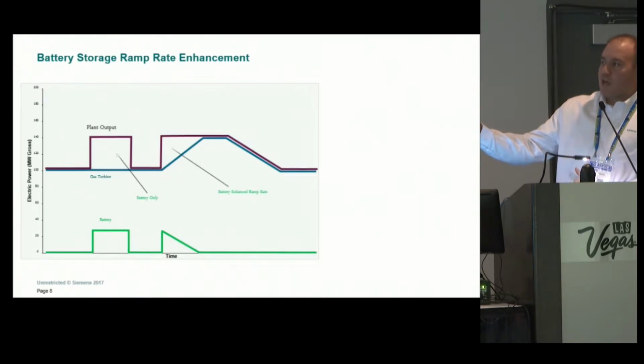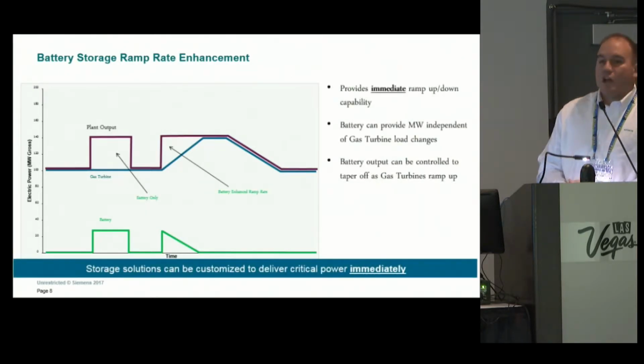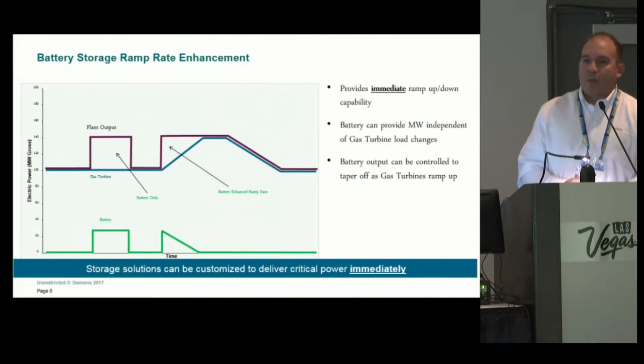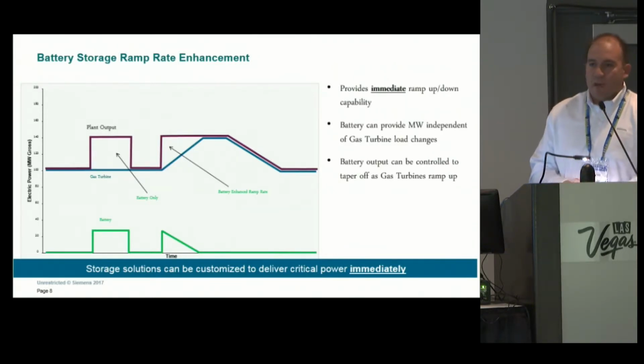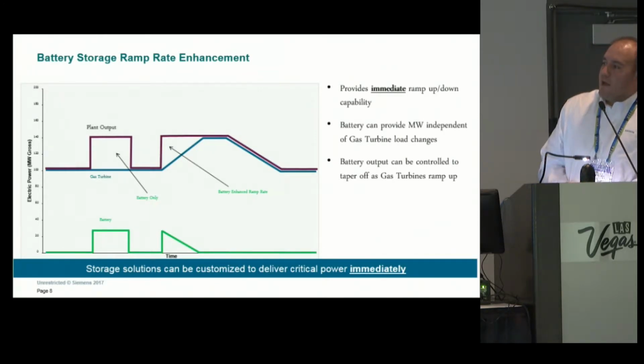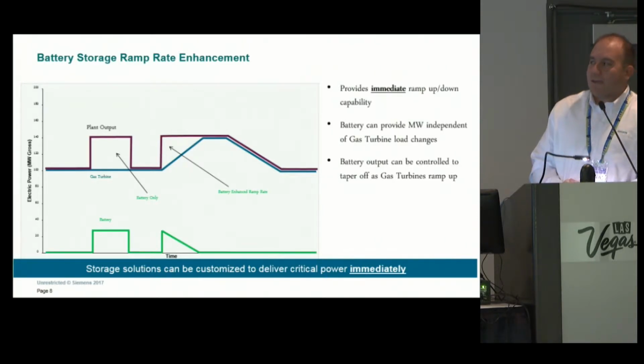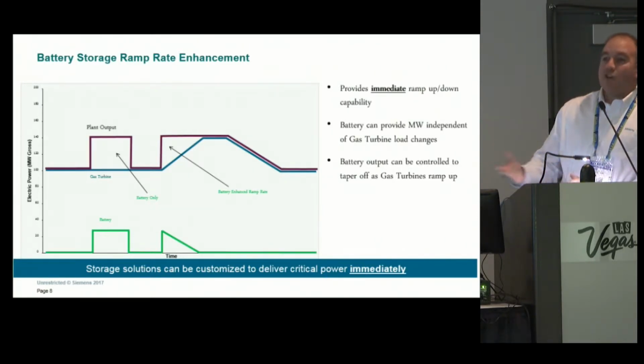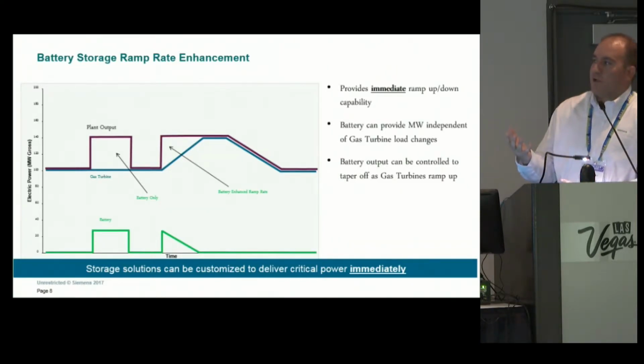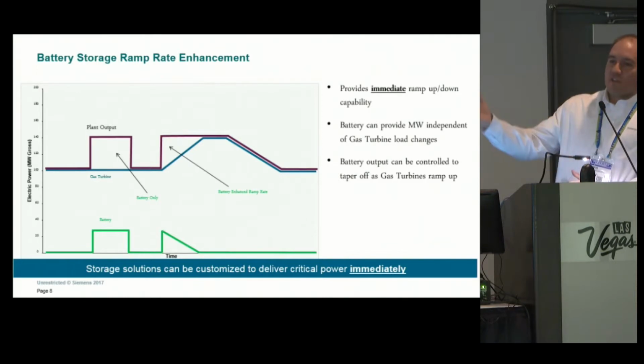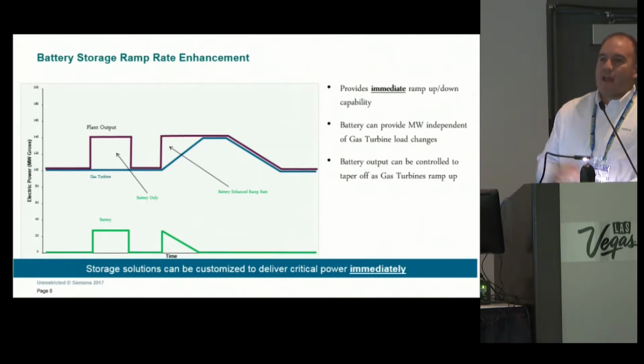Now you can see the blue line is what your gas turbine or your power plant is doing. The green line at the bottom is what your battery's doing. So for that first segment, you're capturing that ramp rate with strictly your battery. It's ramping up and ramping down. Your gas turbine's not doing anything. Then the second is truly what we call a ramp rate enhancement. So you're getting an instantaneous output increase from the battery while your gas turbine or your power plant ramps up normally. And as your gas turbine or power plant ramps up, the battery tapers back out so that the grid sees that output jump instantaneously, and it shows for however long you need it to be there.